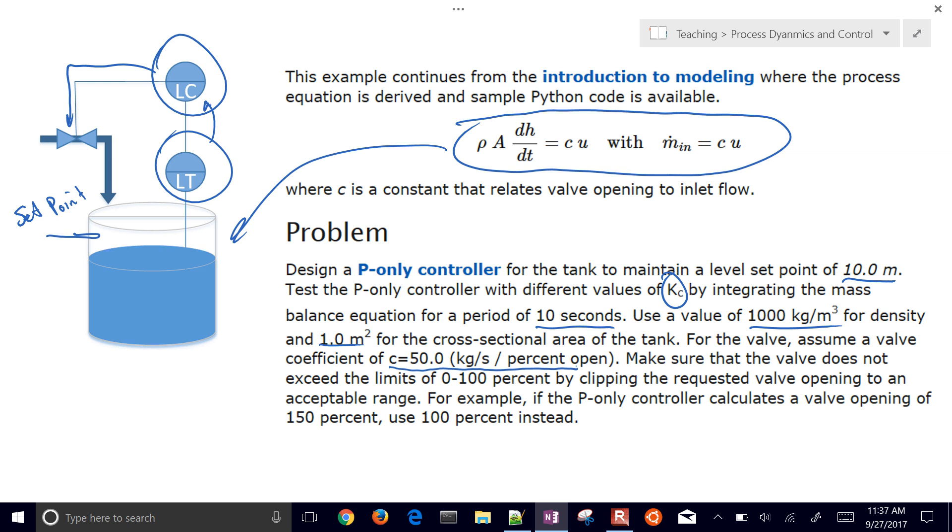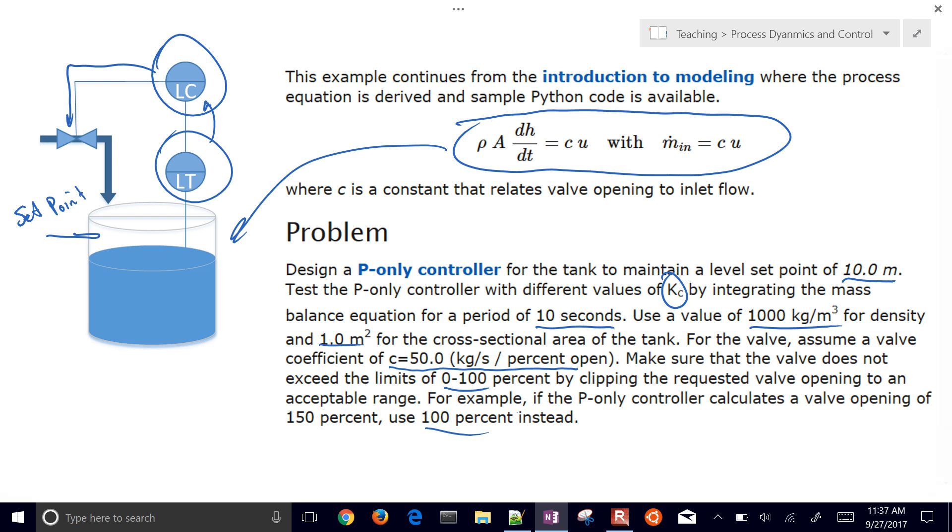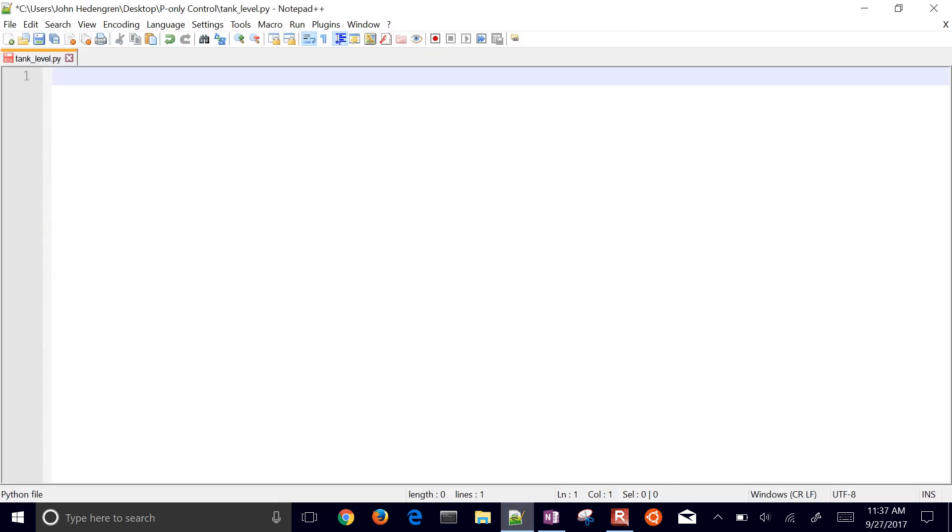Make sure the valve does not exceed the limits of 0 to 100%, and we'll do that by clipping the requested valve opening to an acceptable range. For example, if it requests 150%, we'll use 100% instead. So we'll just clip the controller output. I'm going to develop some example code here and fill in some of the blanks. I'm going to go through this a little bit fast because we've already developed this in a prior simulation.